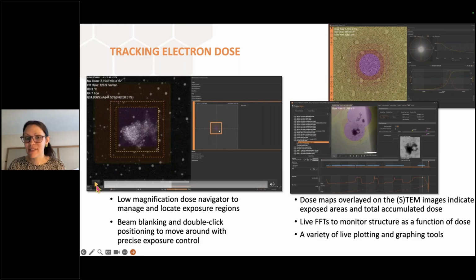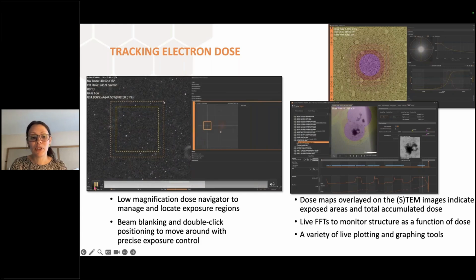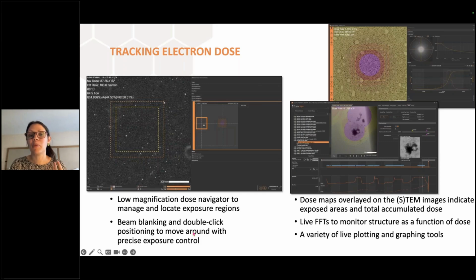If you want to go somewhere else on the stage that has not been touched, it's very easy to see where that is because there's no colorization anywhere else. You can double click and move to a new area. It will blank the beam as you move so you don't just shower everything with dose. And now you can see where you were before. It's going to remember that for you. It's going to keep that history. If you go back to that area later, it's just going to continue to accumulate the amount of dose that's been applied there, and you've got a complete history.